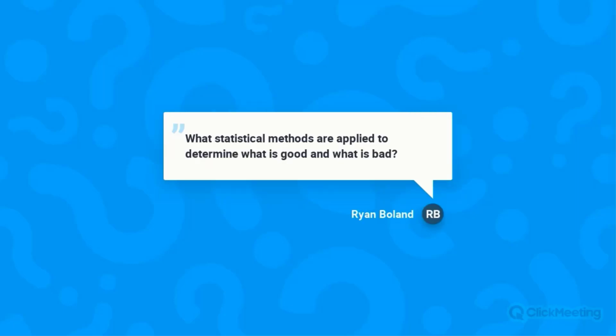Next question: what statistical methods are applied to determine what is good or bad? This goes back to the validation logic mechanism covered throughout the presentation. The statistical method applied is based on the connectivity of the data between the levels. We make sure we're connected at each level, and if we're getting data through that level, we look at all the tags at that level. The statistical analysis basically uses an all-or-else method: if we're getting one data point versus not, we determine if it's a tag issue or an entire level issue. That's the nutshell version. Of course there's a lot more math behind it, but to make it easier for the user to understand, we look level by level to determine where the issue is statistically.